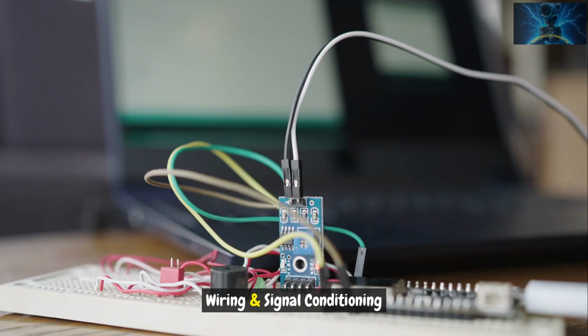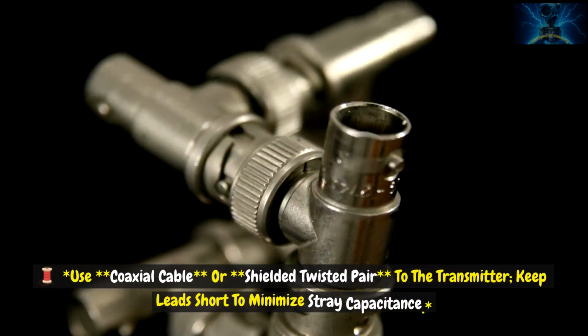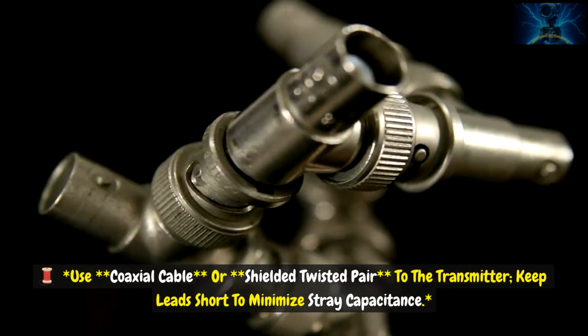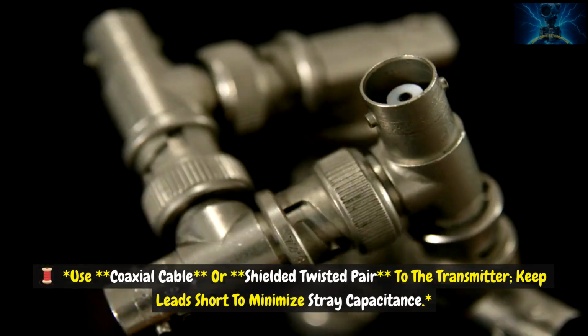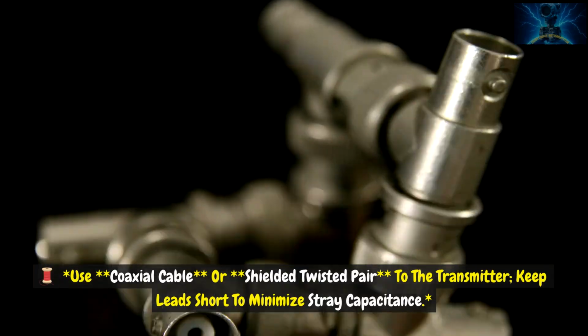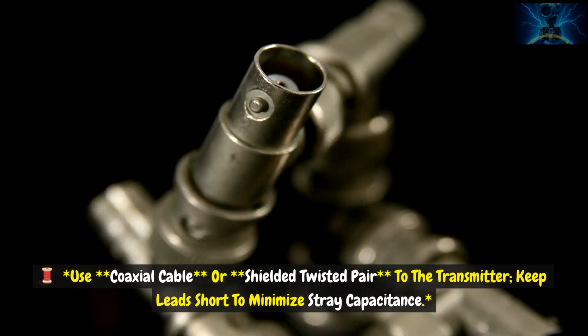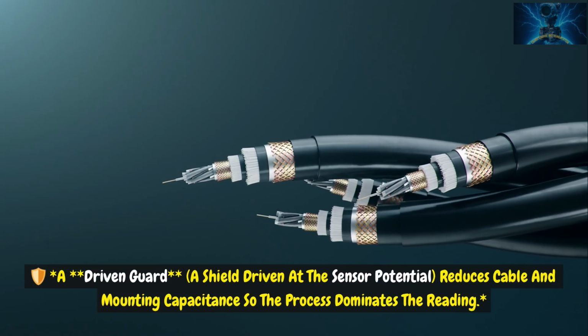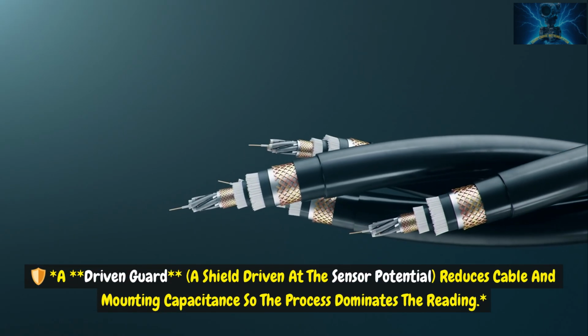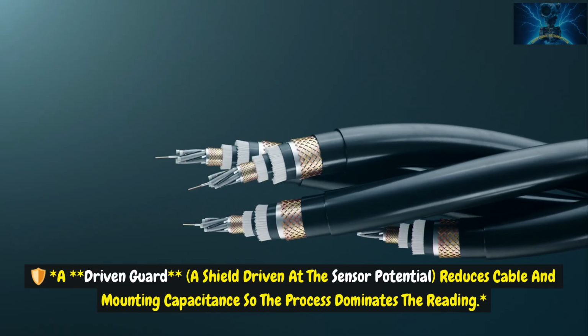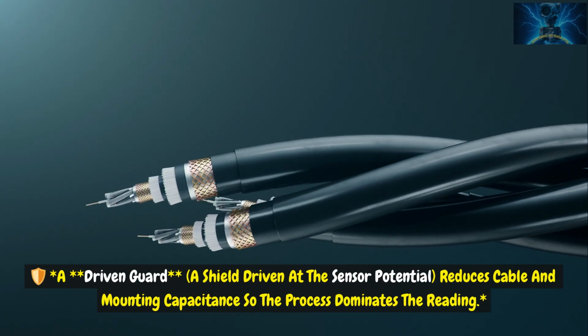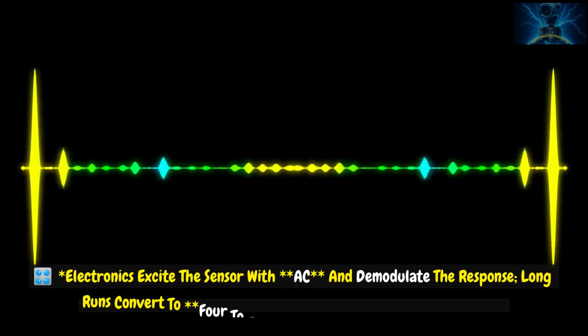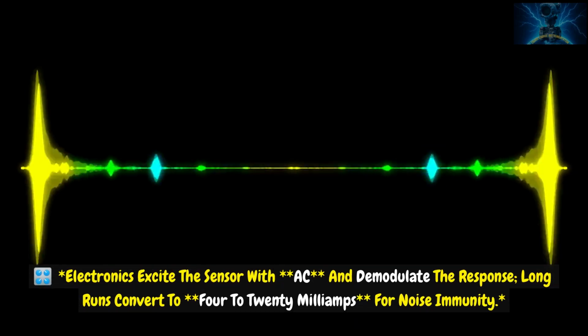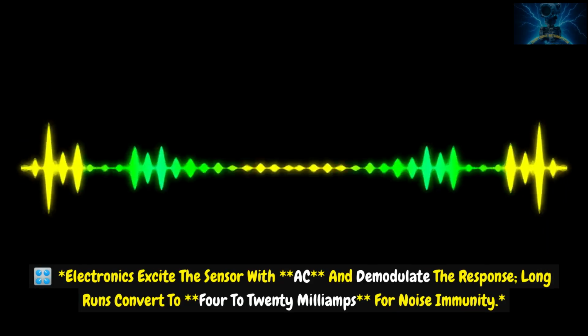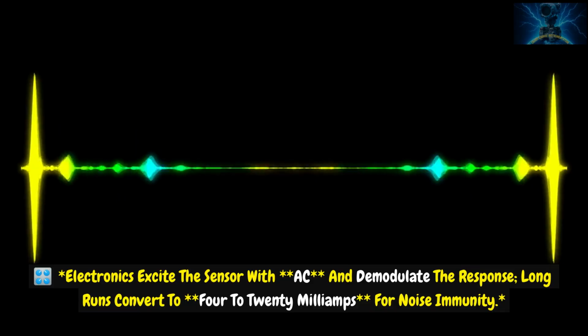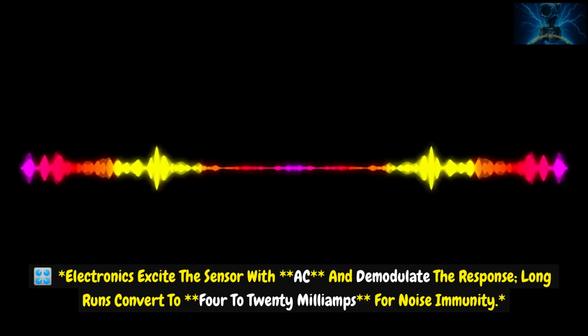Wiring and signal conditioning. Use coaxial cable or shielded twisted pair to the transmitter. Keep leads short to minimize stray capacitance. A driven guard, a shield driven at the sensor potential, reduces cable and mounting capacitance so the process dominates the reading. Electronics excite the sensor with AC and demodulate the response. Long runs convert to 4 to 20 milliamps for noise immunity.